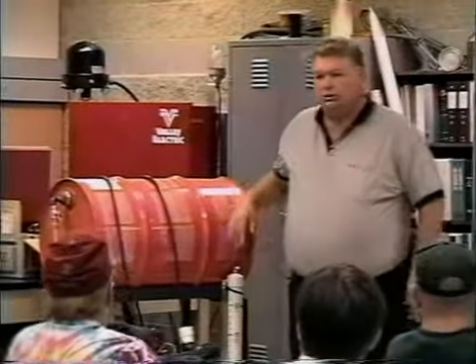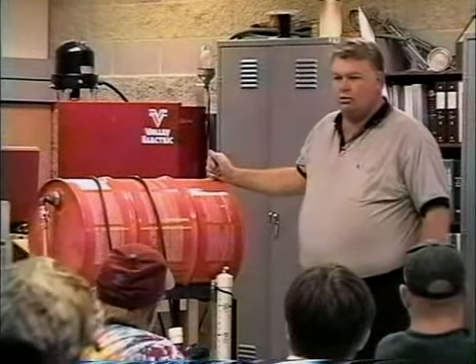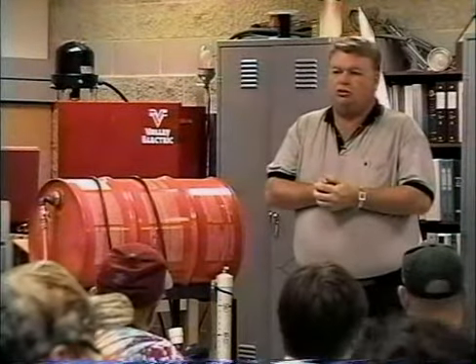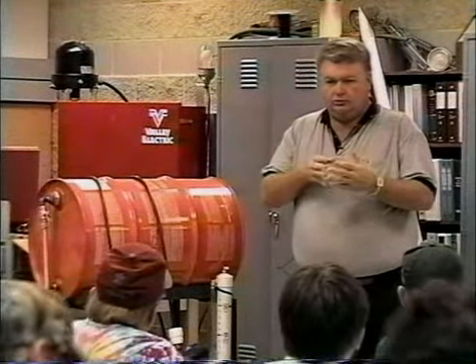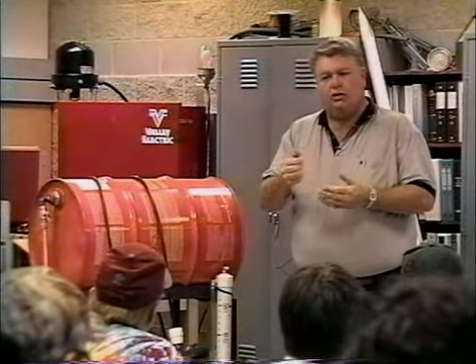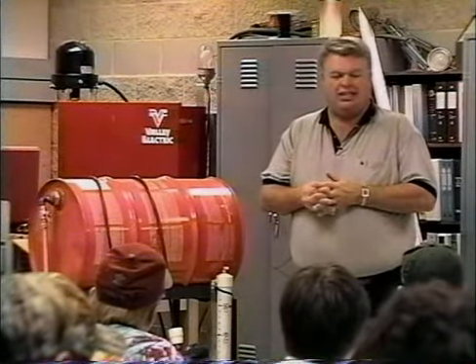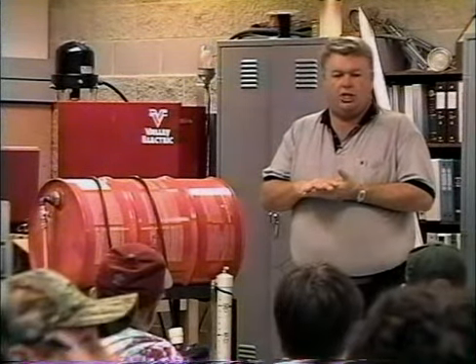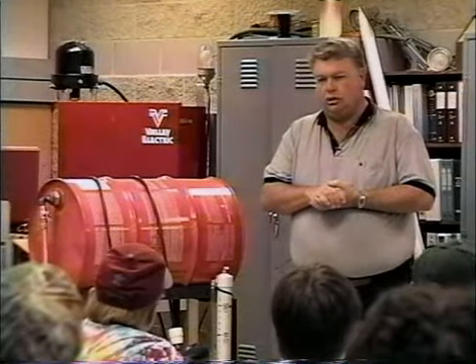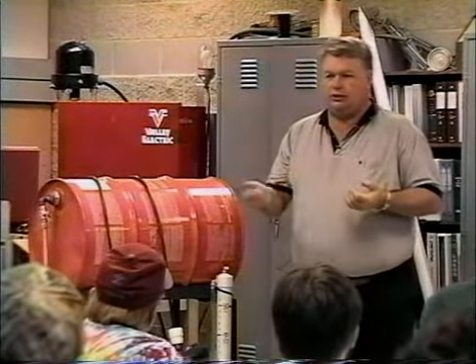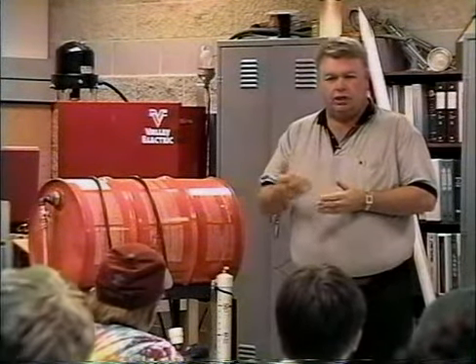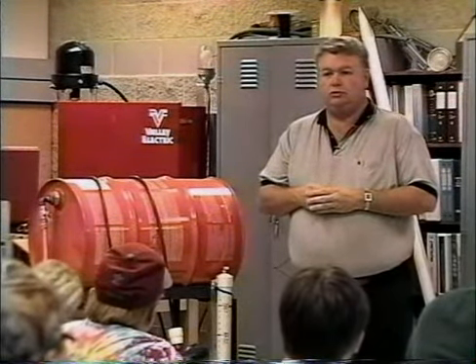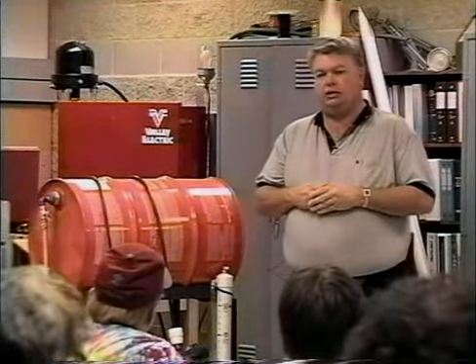Any questions about injection? The diaphragm pump works the same way — exactly — except it doesn't have chemical-to-piston direct contact. In between the piston and the chemical there's a diaphragm — a basically inert material. I think it's a BUNA-N rubber diaphragm that's in there, and virtually any chemical that would come in contact with that will not corrode it. Whereas on that piston pump, we actually have a stainless steel piston in there, but the liquid that the piston is pumping is actually touching the piston itself. Whereas with the diaphragm, we isolate the piston and the entire pump with that diaphragm.